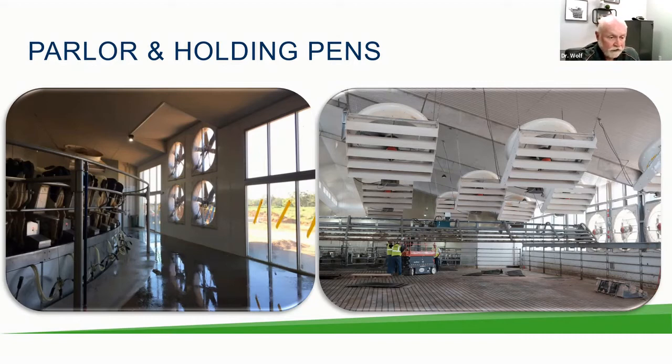On the right, we have a holding pen that has recirculating fans. And again, it can be varying types of fans, as long as they create the proper coverage. But on this right wall over here, these are pressurizing fans, again, pushing in fresh air, and we're going to try to be closer to that 1,000 CFM per cow being pushed into this barn, and at least a one minute air exchange in this area, because of the intensity of the heat that's coming off these cows, along with soakers. And again, high pressure fog can be added to those pressurizing fans to help cool that air along with the soaker system.